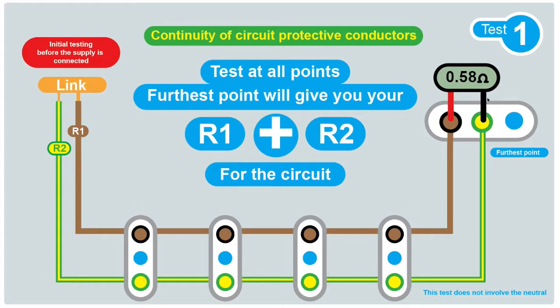The purpose of the test is to verify that the CPC is continuous from the fuse board to every point on the circuit, all the way to the furthest point, and is correctly terminated at each point on the circuit. We do the test by linking out the line and the CPC, R1 plus R2, and we test at each point with our low ohms tester. At the furthest point the reading we take, we record as our R1 plus R2, and we record that on our installation certificate.